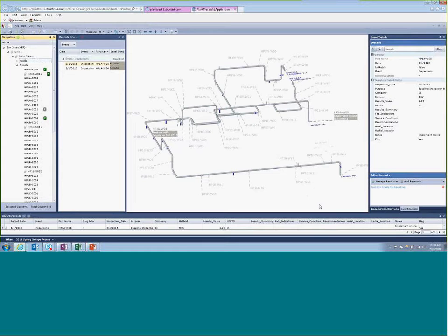This is really nice because it takes the burden off of having to go in and look at it within PlantTrack. Now you know that it's in the background, and I'm at 30% damage consumed. I'll get a notification when I'm at 40%. I know we want to make some actions to either replace it at 50%, whatever the case may be, so you can breathe easily at that point.